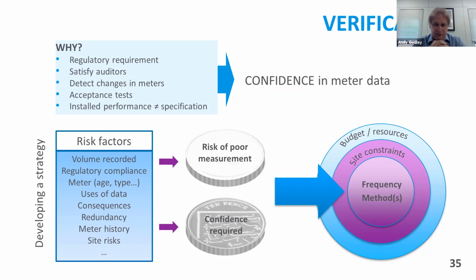But all these different reasons for doing verification really link to us having confidence in the data we get from that meter. So we've done a program of work recently to try and identify how you develop a strategy in relation to a verification program. If you've got lots of large meters within your meter park, you need to think, well, I've only got so much to spend on this verification program. Where do I focus my budget? How do I develop a strategy that will give me the best results for the money I've got available? And we can look at the risk factors associated with those meters. How significant is this meter in terms of how much volume it's recording in my water balance? A more significant meter, you may conclude, has a higher risk. And you can look at all the other factors. This is a very old meter, it's more likely to be having errors. It's a type of meter that I've had problems with before, or it's an individual meter that I've had problems with before. So you can look at all these risk factors and balance them up.